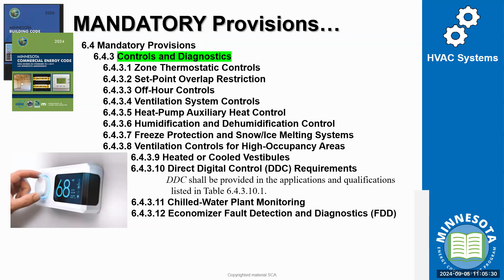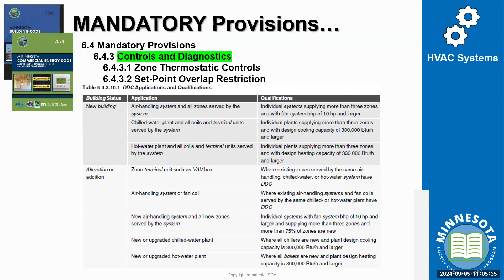Direct digital controls, economizer, fault detection, those types of things — most important to the conversation is recognizing that the notes on what types of controls are being utilized on a particular project need to be incorporated. A lot of times we see those in the section of keyed notes, with a list of different controls and diagnostic distinctions to identify, making sure these systems are tracking the right temperature in the right location to affect the right equipment, and that we're not having this interconnection issue.